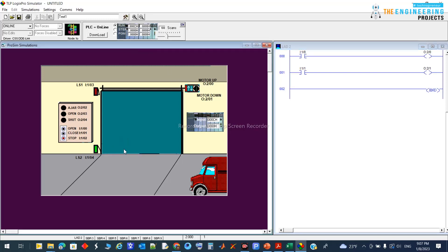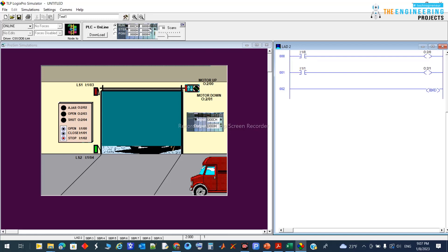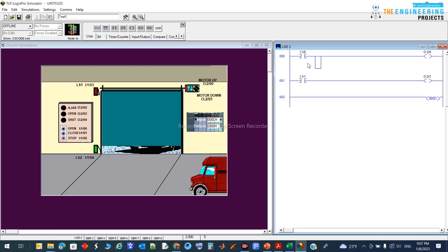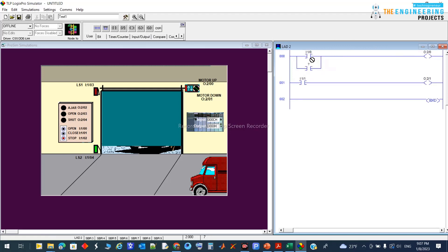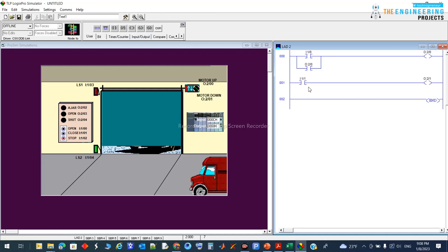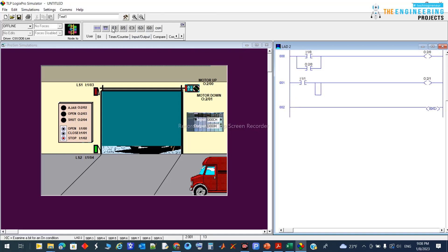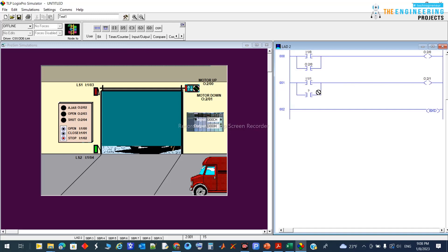You can see: I'm requesting open but the motor stops as soon as I release the button — we need a latch. Let me show you the tools for programming. I'll add a branch for latching on the open rung and the same for the close rung, using the output coil address as the latch contact.